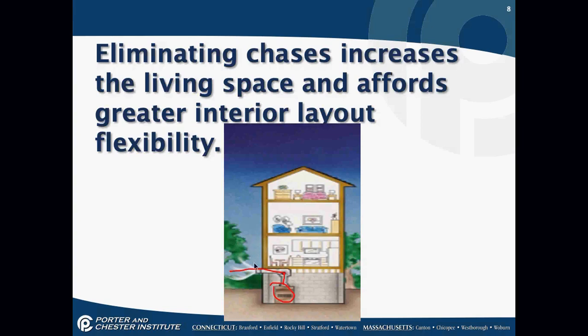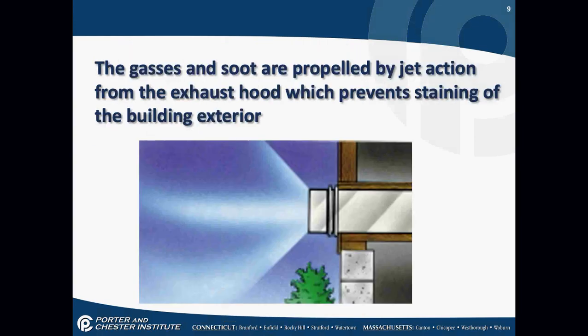Now, there can be no windows around here. There are very strict guidelines on where this can be installed. All gases and soot are propelled by a jet action from the exhaust, which prevents staining of the building exterior. You should never see soot buildups anywhere around here. If there are soot buildups anywhere around there, the power venter is not working properly.